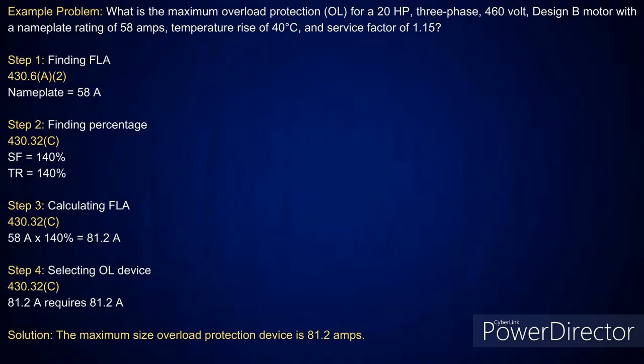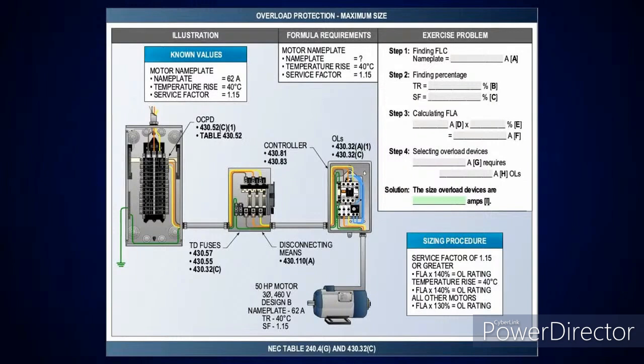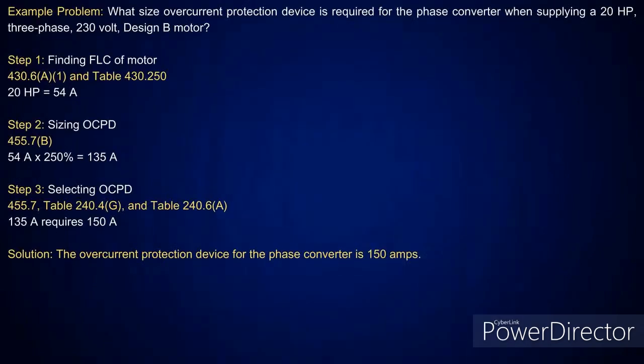So I'm looking here, my temperature rise and service factor meet up, so I know I'm going to do this at 140%. So I'll take 58 amps at 140%. That tells me the maximum size of the overload protection is 81.2 amps. And then here, same motor, 62 amps. I meet my temperature rise and service factor, so I know I'm going to do this at 140% when y'all do your exercise problems.